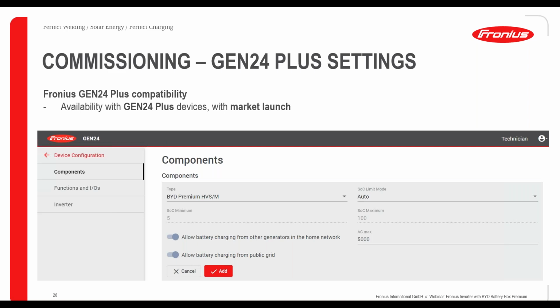For example, the state of charge limit mode. You can set a state of charge limit if you want, for example a minimum state of charge of 10% or 20%, if you choose to have the backup power mode available and want to make sure there is always enough energy stored in the battery system.